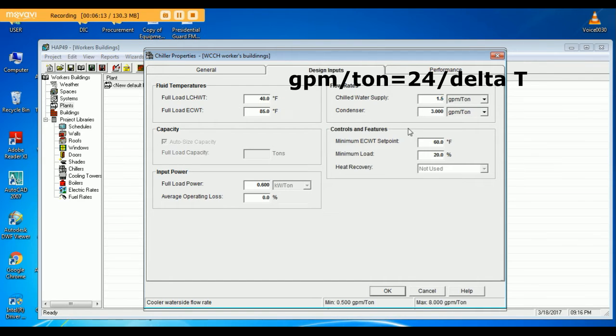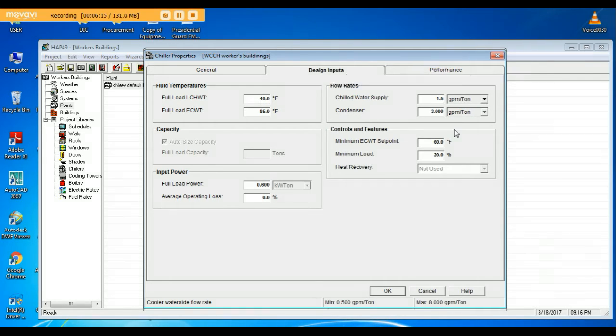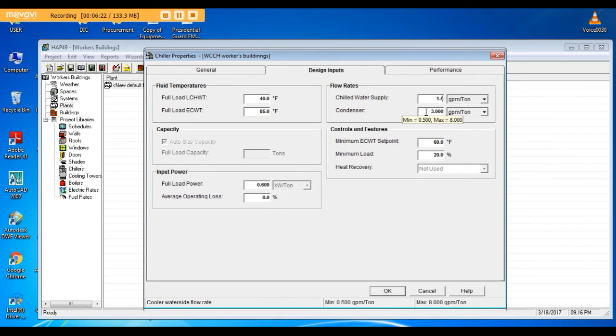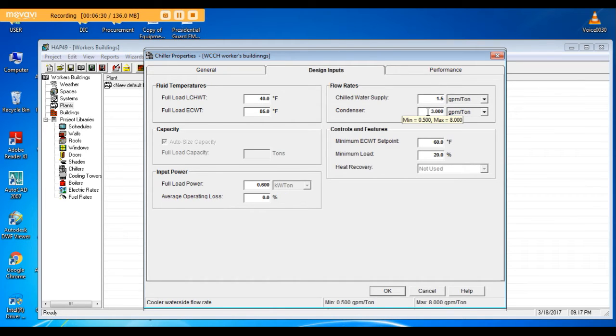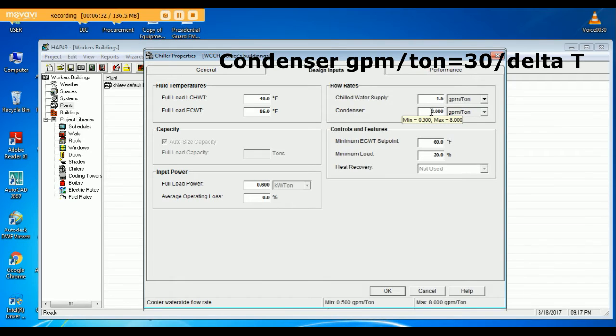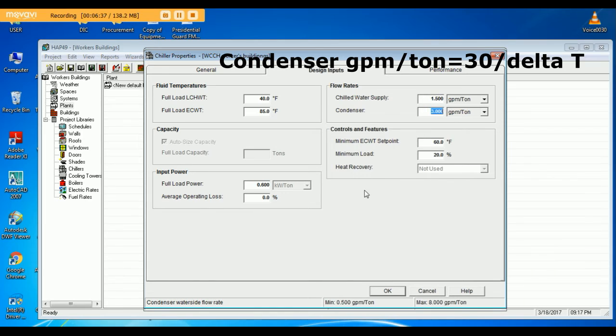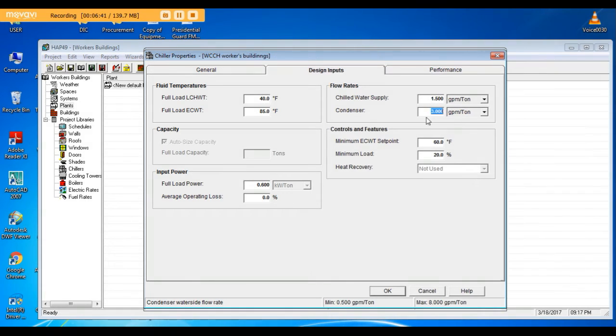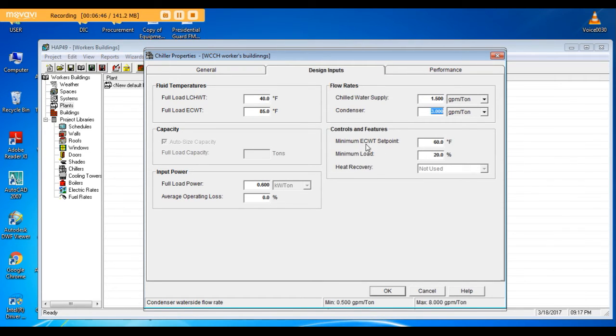Same for condenser water. Condenser water flow depends on the range, that is the difference between the temperature of water entering the tower and water leaving the tower. 3 GPM per ton means we are considering Delta T equal 10 degrees Fahrenheit. I will keep it 3. Minimum load of chiller 20%, I will keep it 20. Minimum entering condenser water temperature set point 60, I will keep it 60.